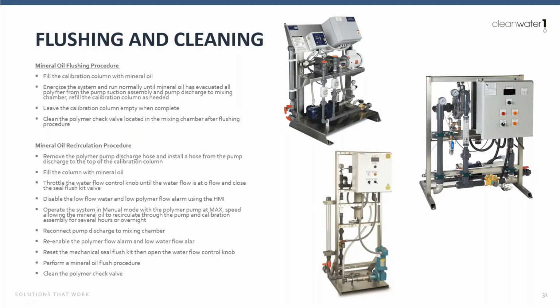The other way to do that is basically create a recirculation line. So you're taking a line from the discharge of the pump into the top of the calibration column. You open those valves and you're cycling that fluid, that mineral oil, through the pump to help clean it. It's really important that we use mineral oil here. We do not want to use water. Again, it's the same aspect that we talked about with the check valve, where as soon as polymer is introduced to water, it starts to react, right? So we can cause plugging all over. So cleaning procedures for anything that is in contact with neat polymer needs to be done with mineral oil.